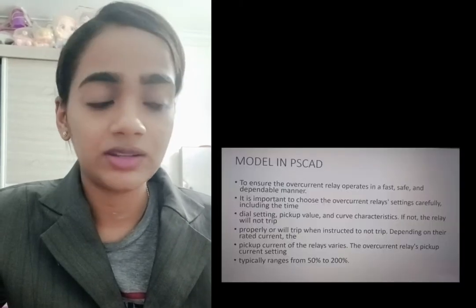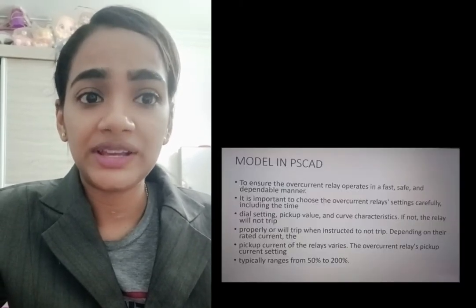The circuit was used to investigate the performance of the overcurrent relay when subjected to faults, characteristic curve standards, and DG installations. The major components and parameters of the model are a 3 phase voltage source, 50 Hz, 132 kilovolt phase voltage. Next, the 3 phase fault block introduces single phase to ground, double phase to ground, and 3 phase to ground faults. The duration of the simulation time is 10 seconds and the time to apply the fault is 1 second.